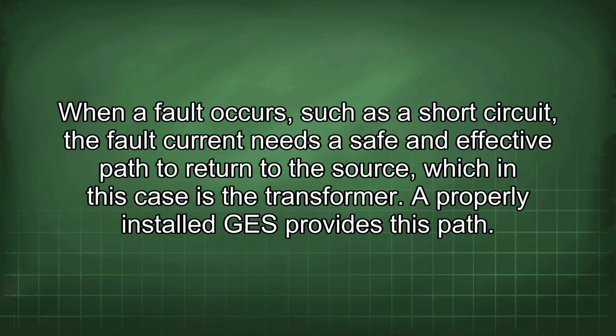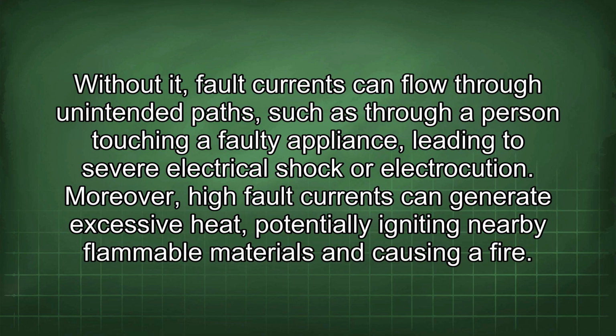When a fault occurs, such as a short circuit, the fault current needs a safe and effective path to return to the source, which in this case is the transformer. A properly installed GES provides this path. Without it, fault currents can flow through unintended paths, such as through a person touching a faulty appliance, leading to severe electrical shock or electrocution. Moreover, high fault currents can generate excessive heat, potentially igniting nearby flammable materials and causing a fire.